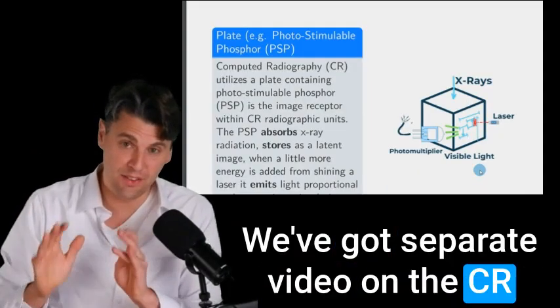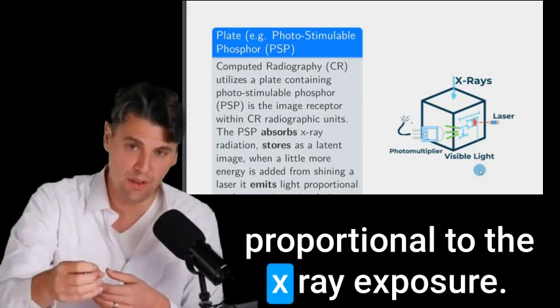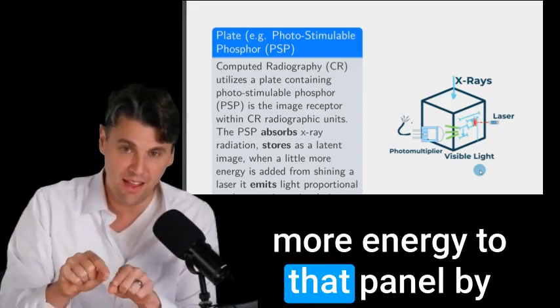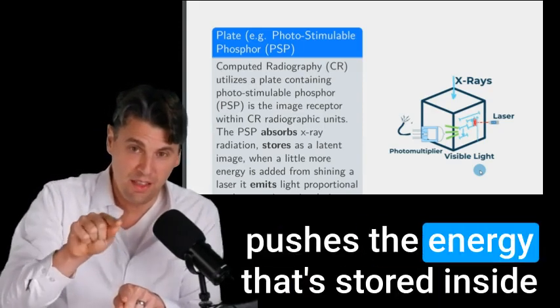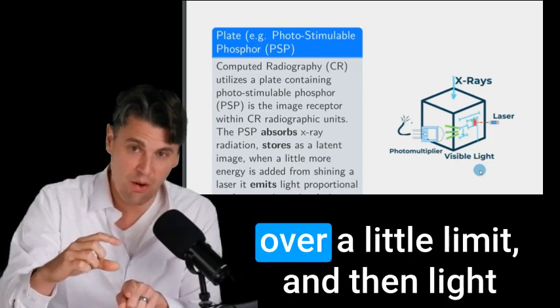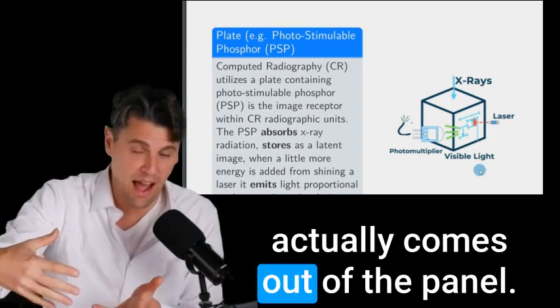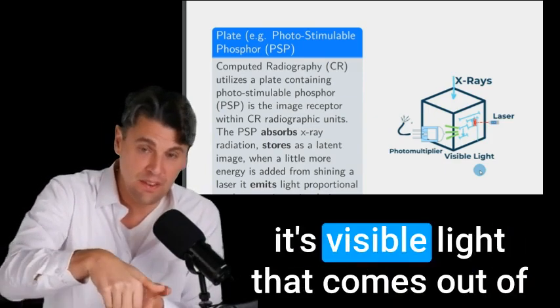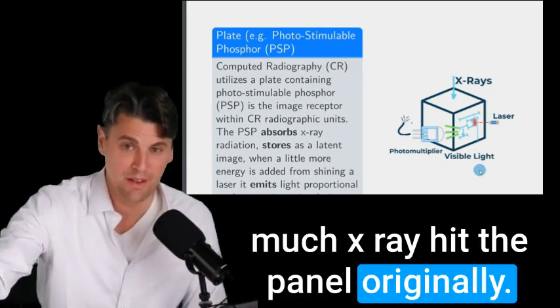We've got separate video on the CR panels themselves. They store a signal, which is proportional to the x-ray exposure. And when you add a little bit more energy to that panel by shooting light on it, it actually pushes the energy that's stored inside over a little limit, and then light actually comes out of the panel. So if you shine a laser on it, then it's visible light that comes out of the panel that's proportional to how much x-ray hit the panel originally.